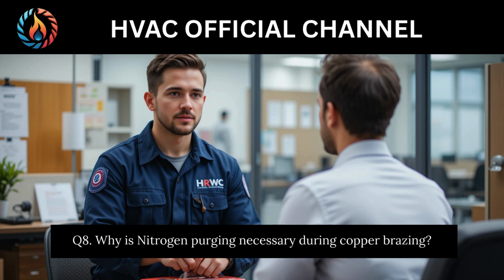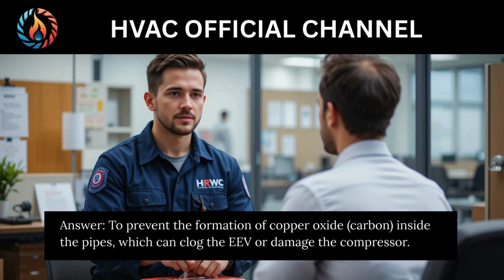Q8. Why is nitrogen purging necessary during copper brazing? Answer. To prevent the formation of copper oxide inside the pipes, which can clog the EEV or damage the compressor.